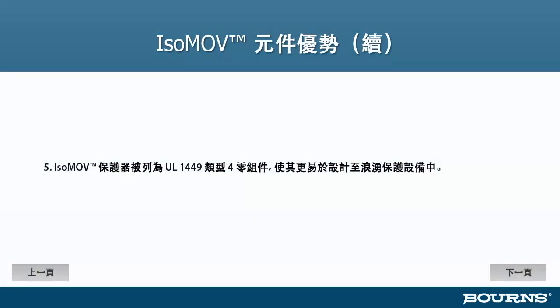IsoMOV hybrid protectors are listed as UL 1449 Type 4 component assemblies. If you're an experienced surge protection device designer, you know what that means. You know that's going to make the UL 1449 qualification of your product a lot easier. There's an assortment of tests you're not going to have to do, because you're already walking in with a rated component assembly. That saves SPD designers a lot of time and headaches.